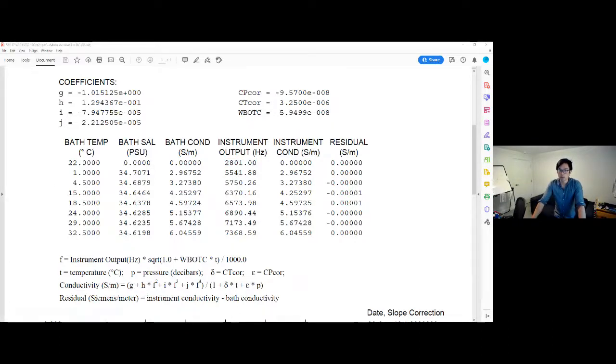Yeah, Greg, you're going to want to send your output format to 3, so that's the decimal data for that as well. And then also, the command is min cond freq. The reason why I didn't accept mine is because I code a lot and I put spaces in between, so no spaces in there.